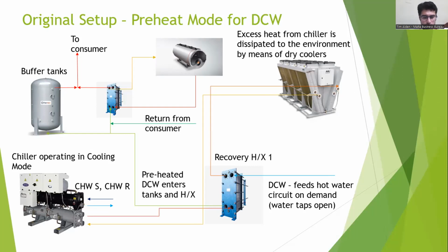With 50 degrees, I can preheat the incoming cold water before it goes to the boilers. So what the old system did was this: I'm getting water at 23 degrees, or maybe even 12 degrees in winter, coming in and exchanging heat with the condensing side of the chiller, which is at about 46 or 48, and it's preheating the water.